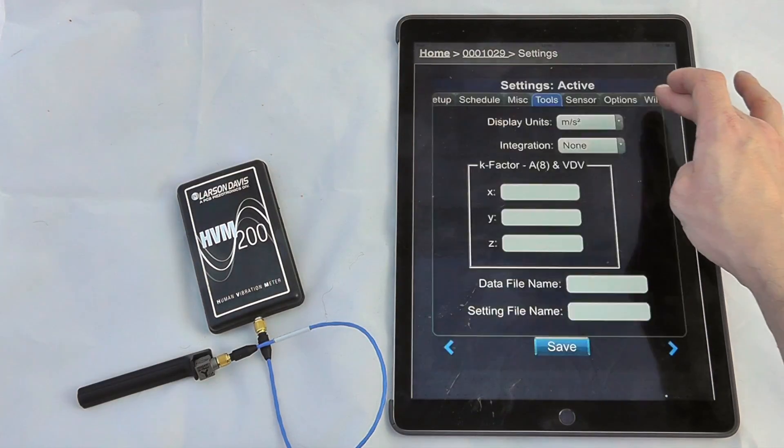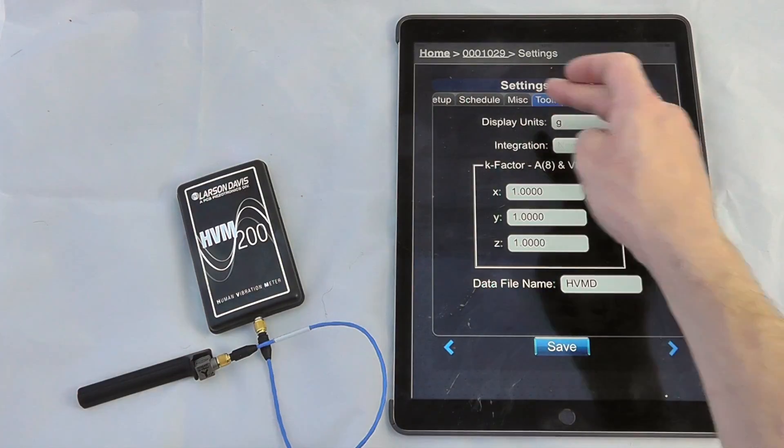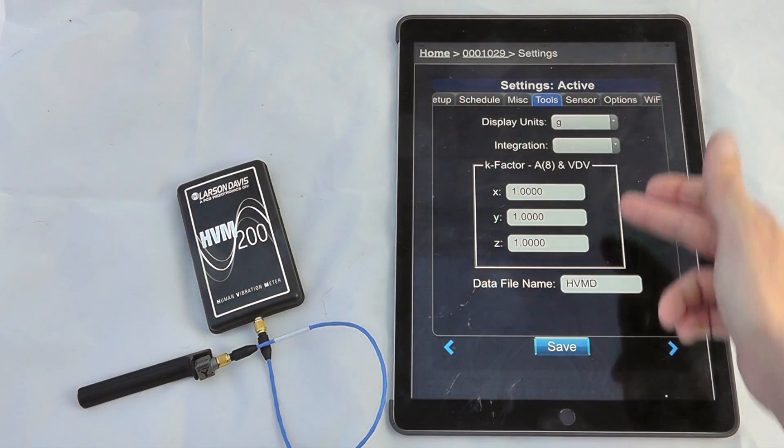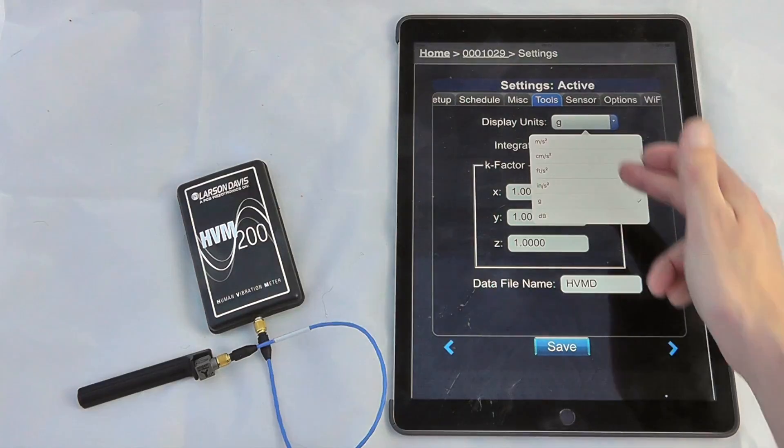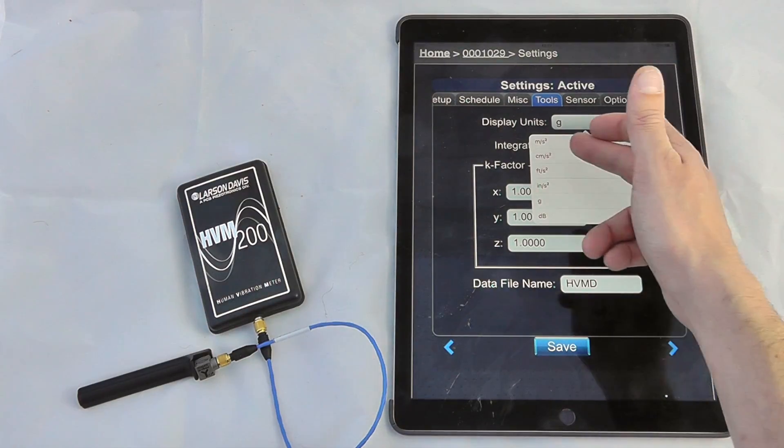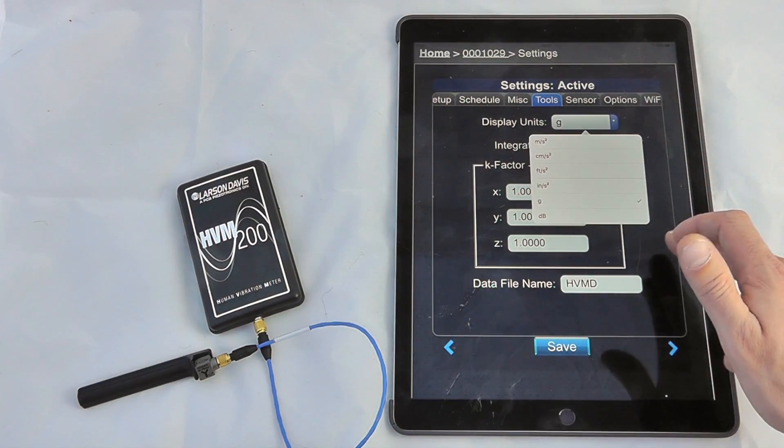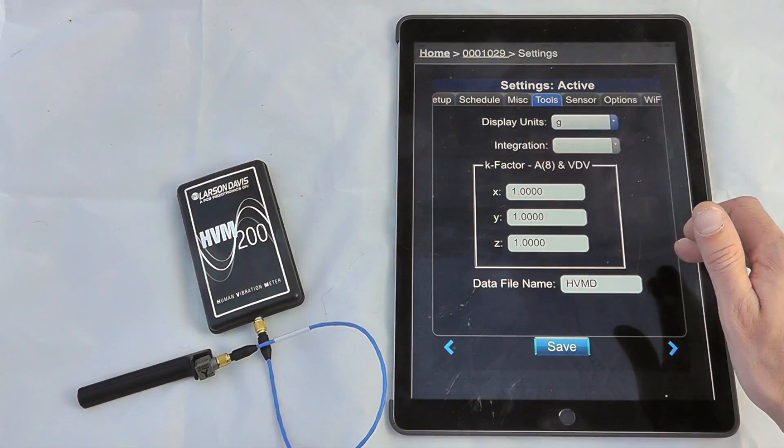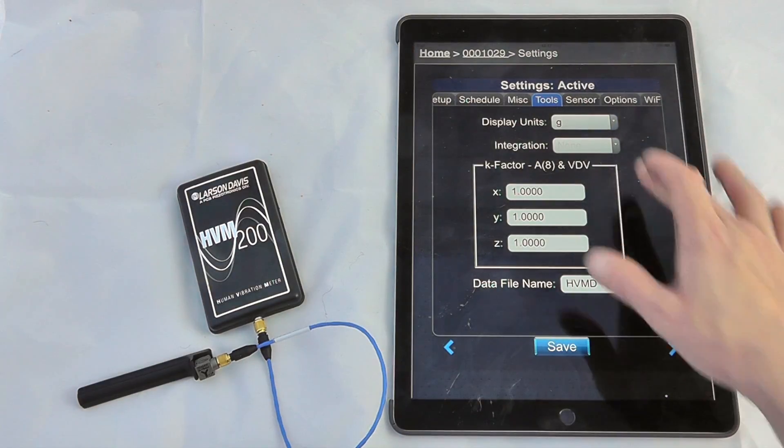We can look at any tools, so we can look at the display units, whether they're in G, meters per second squared, centimeters per second squared, etc. Now ordinarily we'd be using meters per second squared for hand arm vibration measurements.